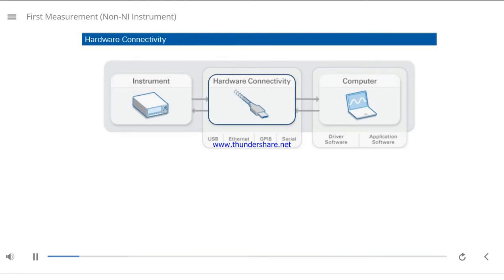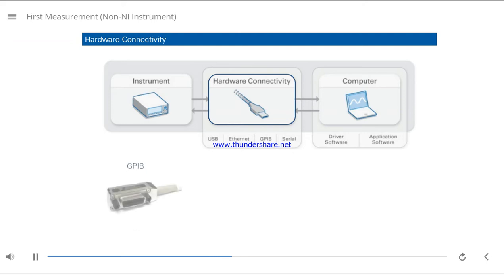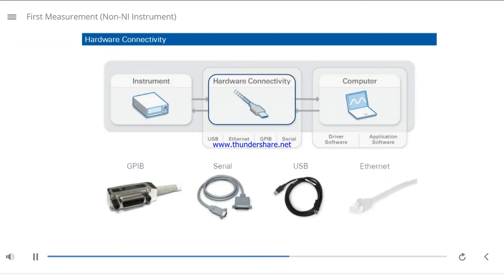Hardware connectivity refers to the physical cable connecting the instrument and also the communication protocol, or bus. Common bus types include GPIB, serial, USB, and Ethernet. Different buses have different capabilities for latency and bandwidth. Instruments often have multiple ports for hardware connectivity options.